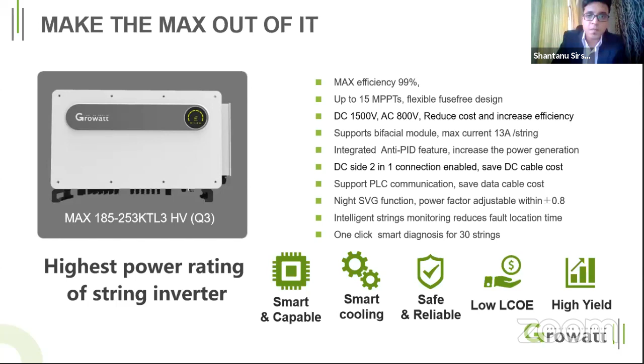High precision string monitoring: with the MAX series, we provide individual string monitoring up to 30 numbers. For example, the 400 volt inverter has 14 individual string monitoring, while the 1500 volt inverter has individual string monitoring up to 30 numbers. We can get individual sampling for each string on all these inverters, making it very easy for troubleshooting and maintenance, and easy to pinpoint which string is giving a particular error.